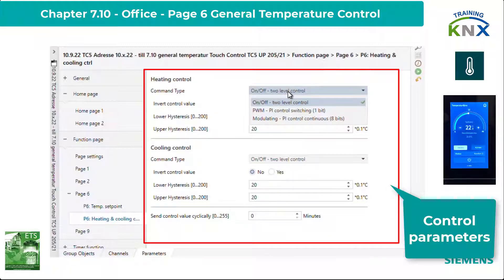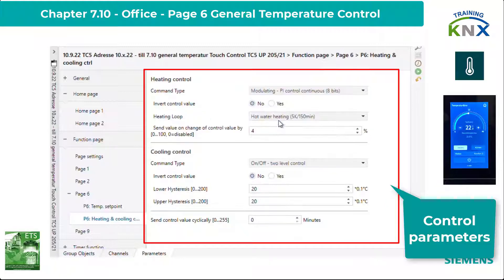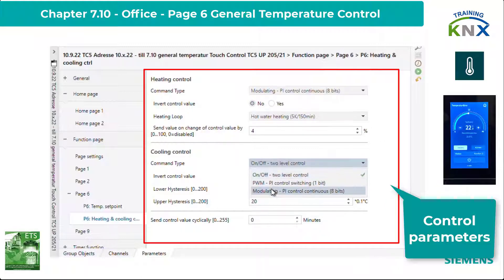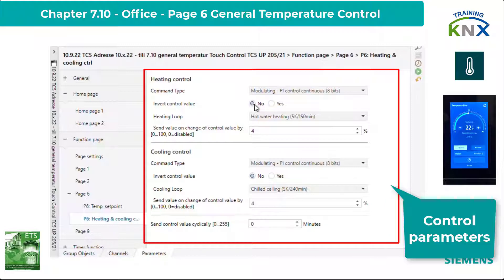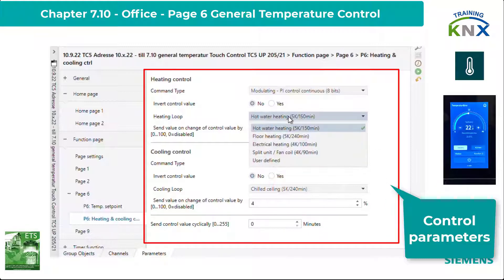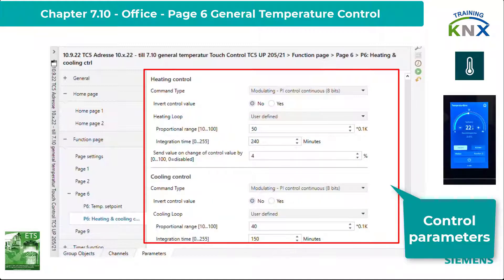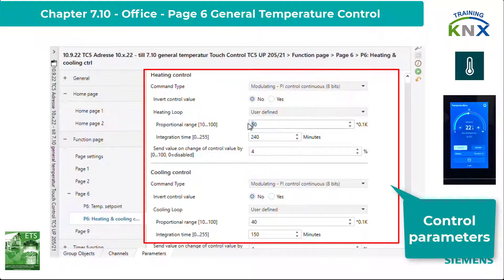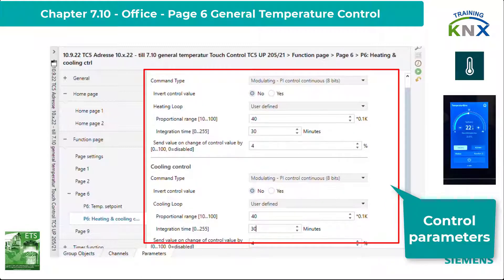With this setting, the user can readjust all normal operating modes at once during operation, always with the parameterized spacing. The setpoints for the building protection mode can be set individually. The values of the setpoint offset visible here are standard: 2 Kelvin offset each for standby and 4 Kelvin offset each for eco mode — nothing needs to be changed here. The last step is to enter or check the parameters for the control itself. As mentioned at the beginning, we set the continuous PI control via 8-bit telegrams.